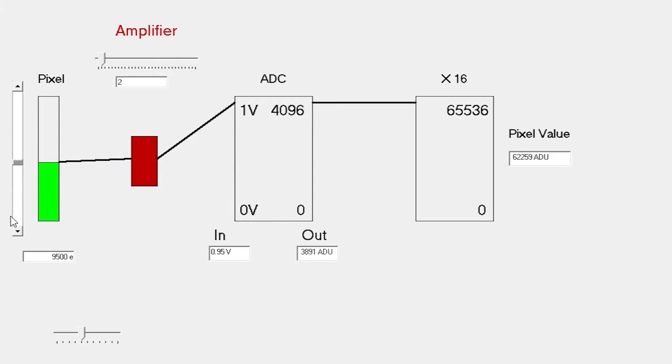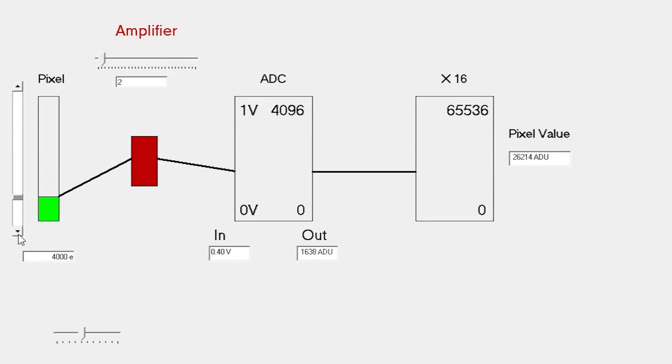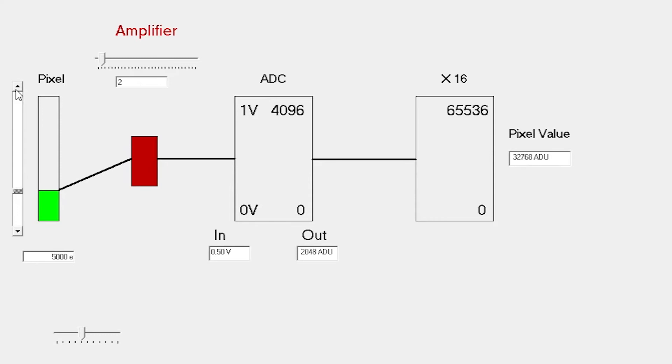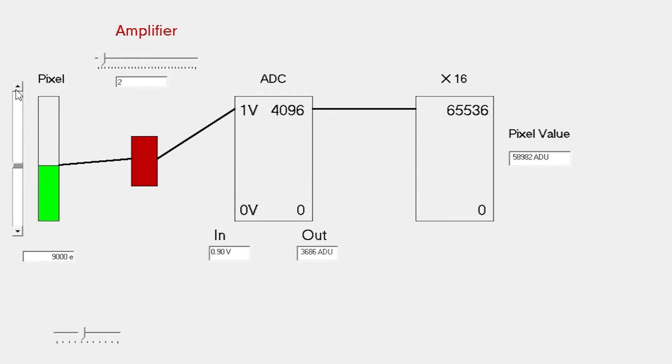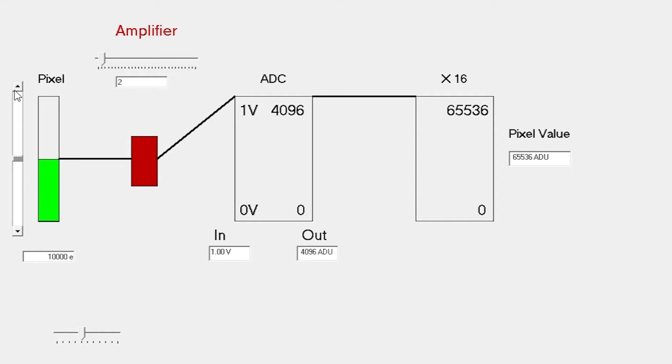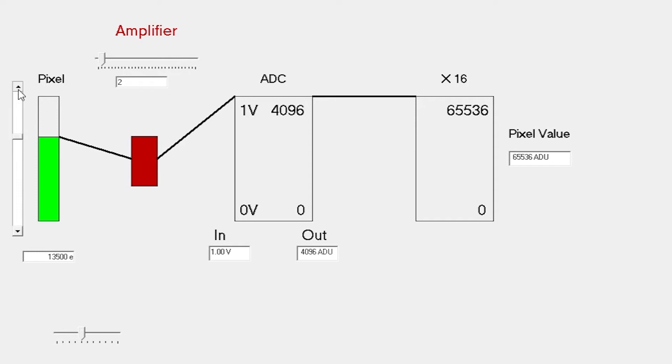As we increase the number of electrons within the pixel, we get an increasing pixel value. But there comes a point at which the imaging chain itself saturates. At a gain of 2, it saturates around half full well depth. Around 10,000 electrons gives the full 65,000 output at the end of the chain. It doesn't really matter then however much we increase the number of electrons. Basically we're stuck. We can't report a value greater than 65,000.